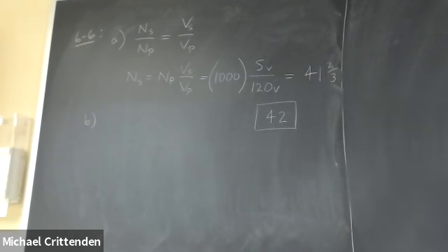If you don't have that self-induced voltage, then all that's holding back the current is Ohm's law. The person who designed the transformer tried to have as few ohms as possible for the internal resistance of the coil. So you put 120 volts on there, and you're probably going to get 20, 30, or 40 amps going through. It's going to melt the insulation off the coil.